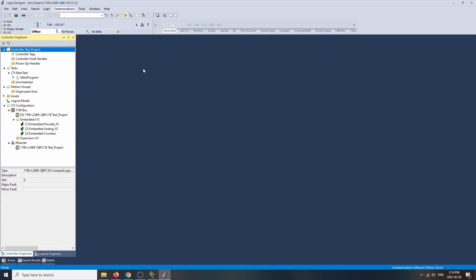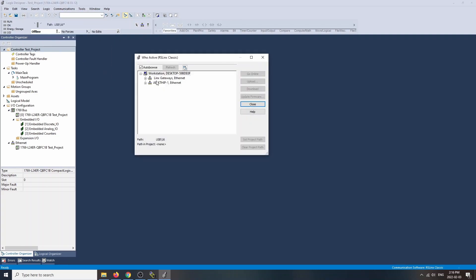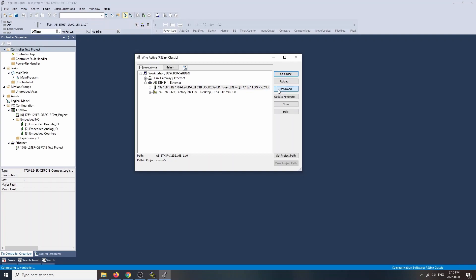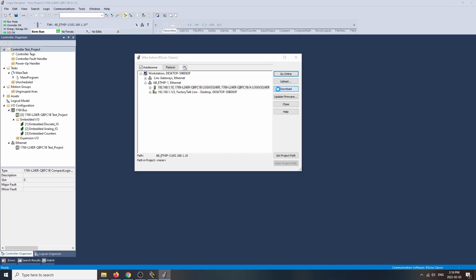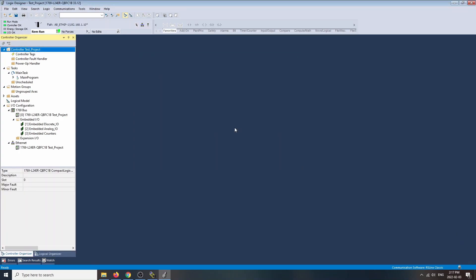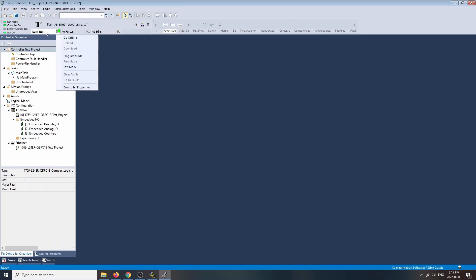Go to Communications, then Who Active. Now we've got our Ethernet connection. Opening it up — there is our PLC at 192.168.1.10. We can go online or download the existing project. Let's download it just in case something else was there. Download is done. Changing the controller back to remote run mode. We're now in remote run — run mode is good, controller is OK, and IO is OK.